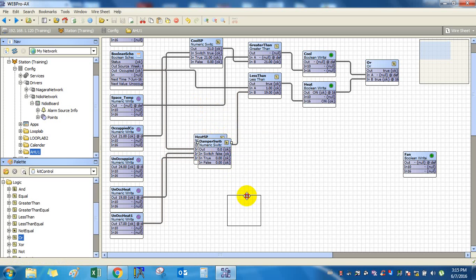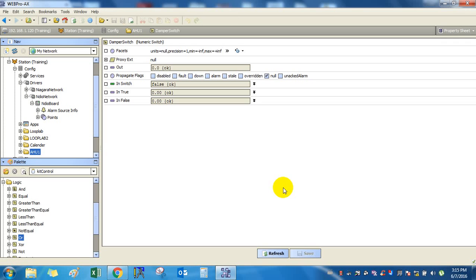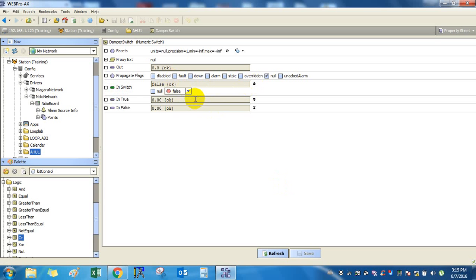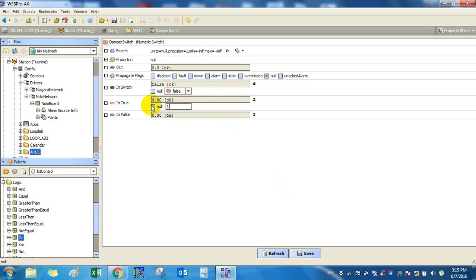Double click here. Configure the true pin as 100 and false pin as 0. That means whenever your fan is running, your damper will be 100% open, and whenever your fan is off, your damper will be at 0% position. So you will see these values here, 100 and 0.